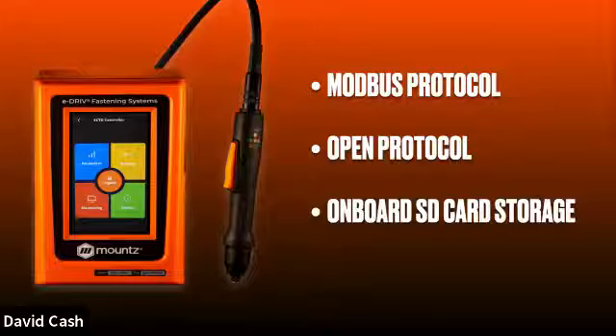There are settings in the controller that won't allow it to function without the SD card, so you have a guarantee the product is capturing data, since the system won't run without the SD card in it. Those are the different ways we can do that. You can either have the data transferred via Modbus and Open Protocol out of the Ethernet connection, or we also have an RS-232 port where we can run that information out as well.